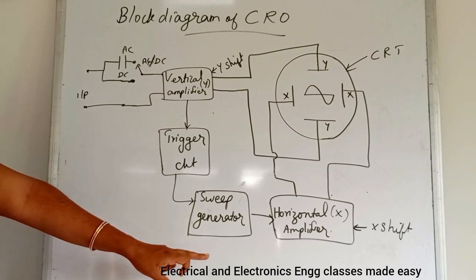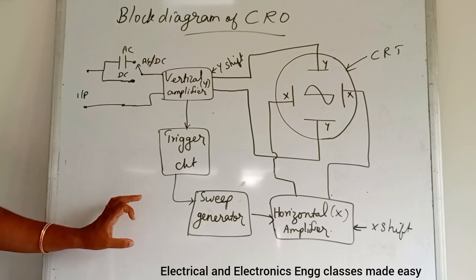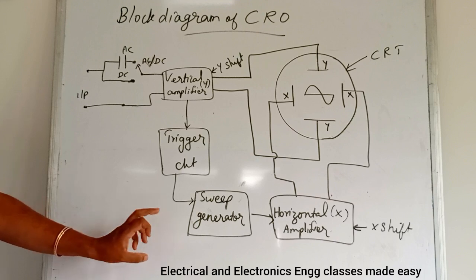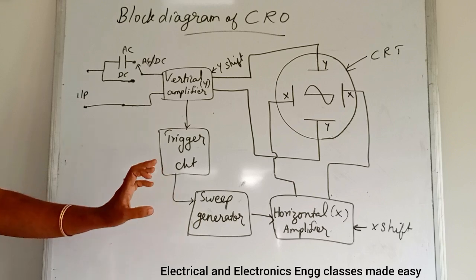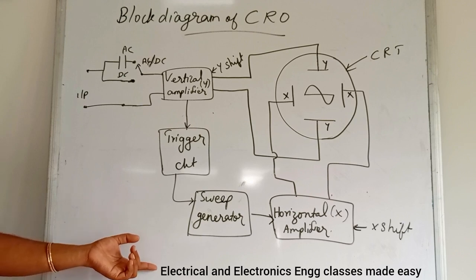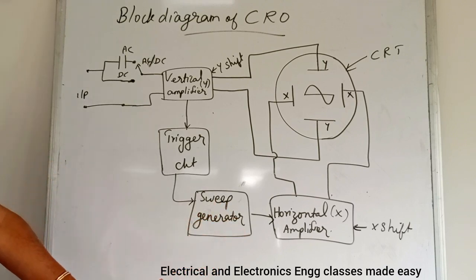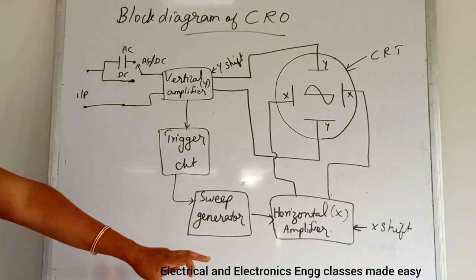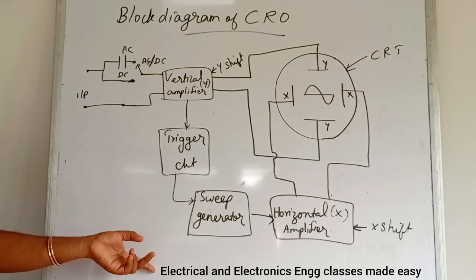The trigger circuit is used to start the horizontal sweep at a specific instant with respect to the waveform under observation. Triggering or synchronization is achieved by making a connection between the Y amplifier and the time base, allowing a stationary pattern to be observed on the screen. The sweep generator produces a sawtooth voltage and causes a horizontal deflection of the spot proportional to time. The horizontal amplifier, also called the X amplifier, amplifies the sawtooth time base voltage and feeds it to the X plate.